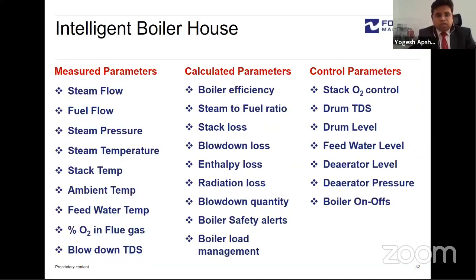So these are the parameters which we measure, which are calculated, and which are the control parameters. There is a list of parameters which are very important to understand the health of the boiler, and whether the boiler is running at the optimum capacity and the optimum efficiency, and what are the control parameters and what are the corrective actions which you have to do. So this makes the boiler house intelligent in its own manner.